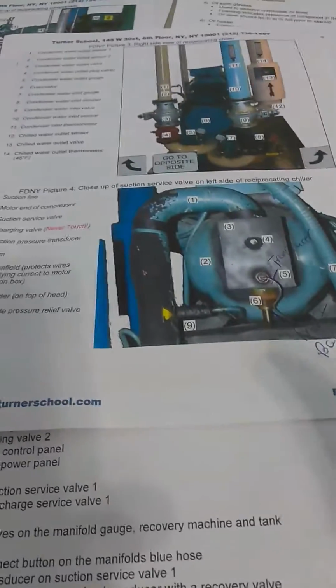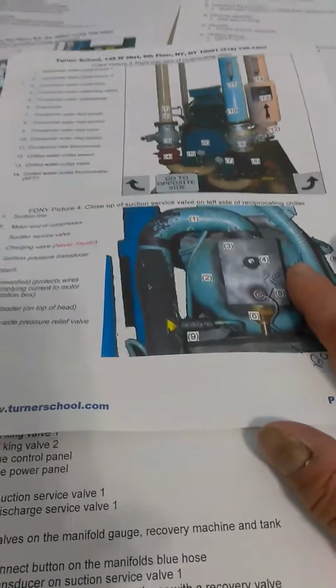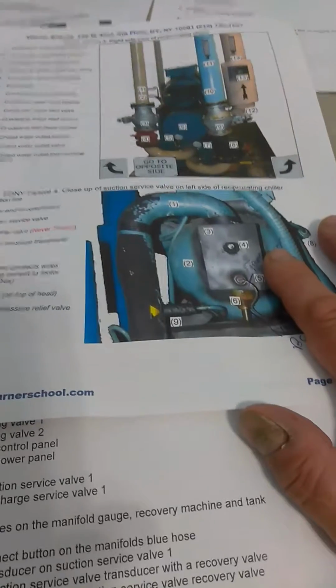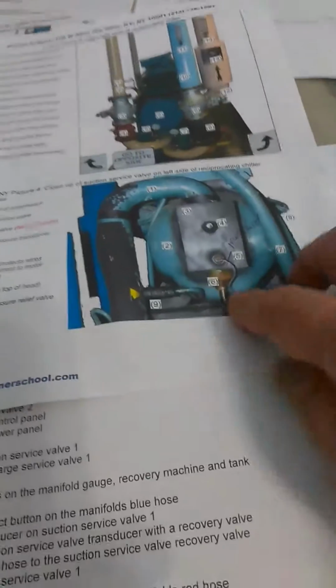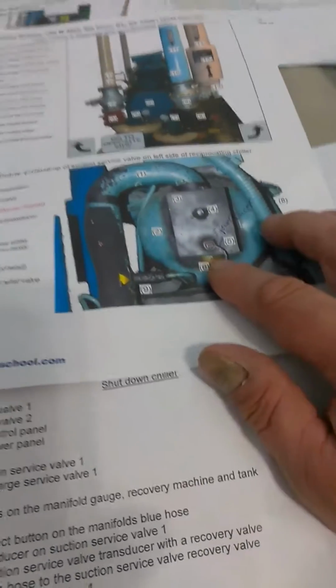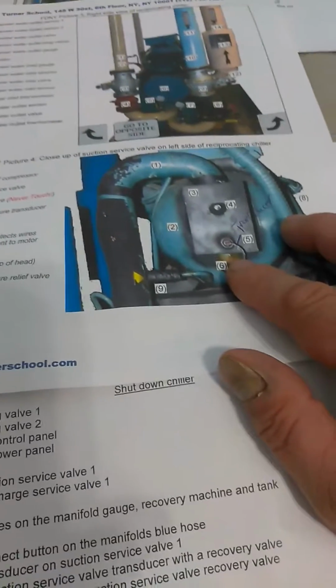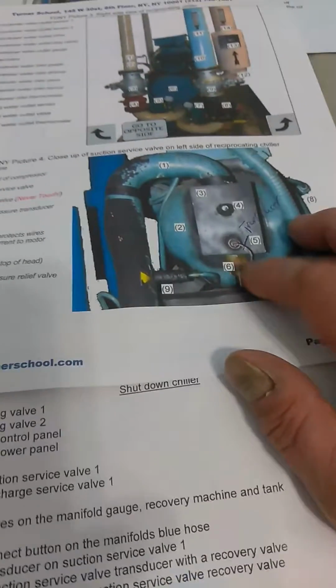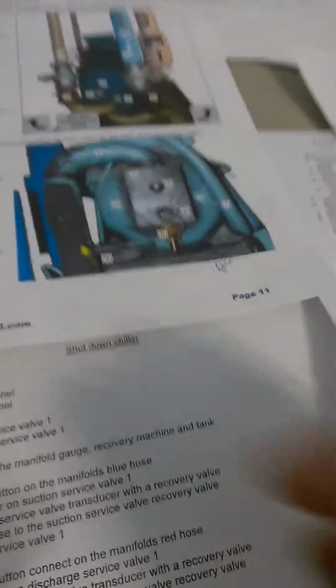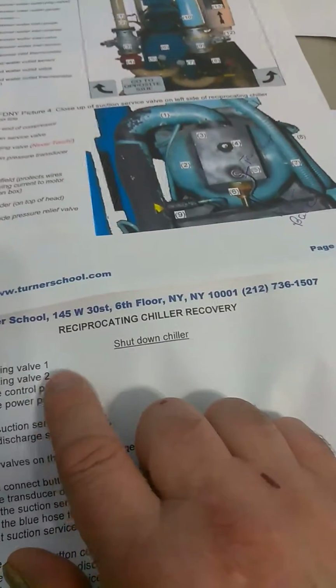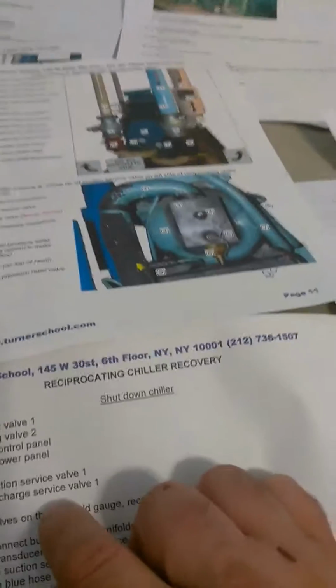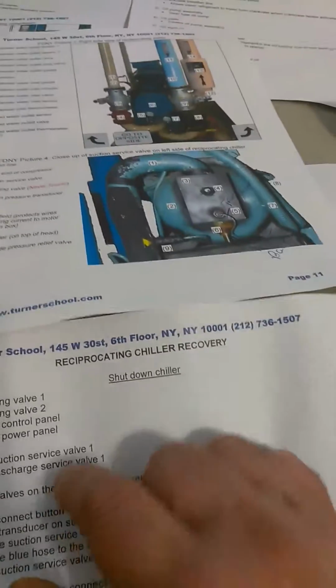Hold on, I'm doing something. Alright. Back seat the suction service valve. Chiller was shutting it down. Front seat the king valve. Back seat the suction service valve. Back seat the discharge service valve.